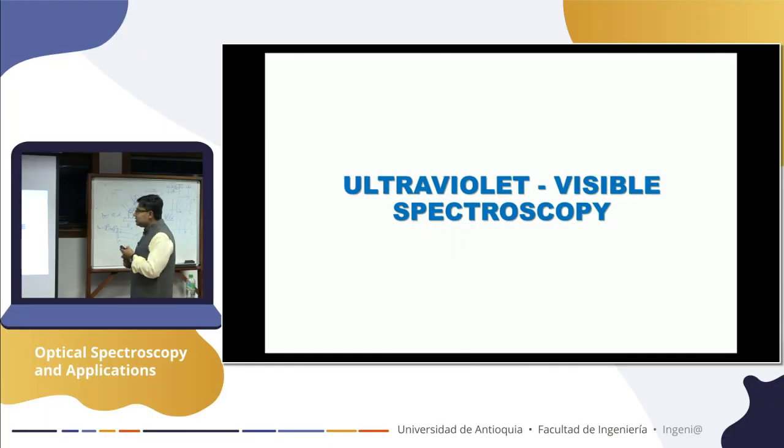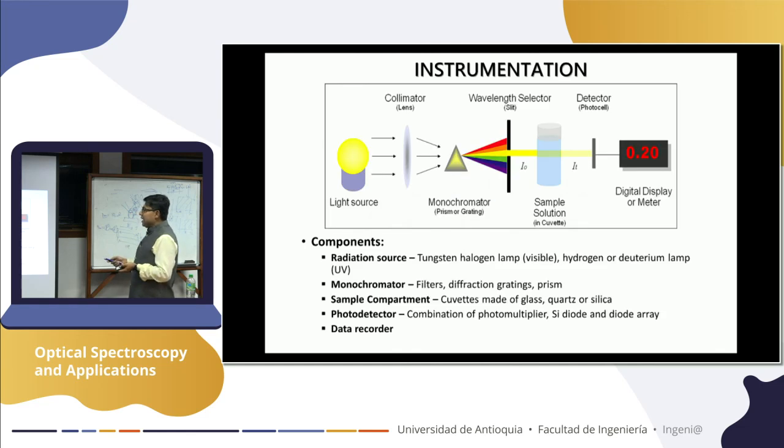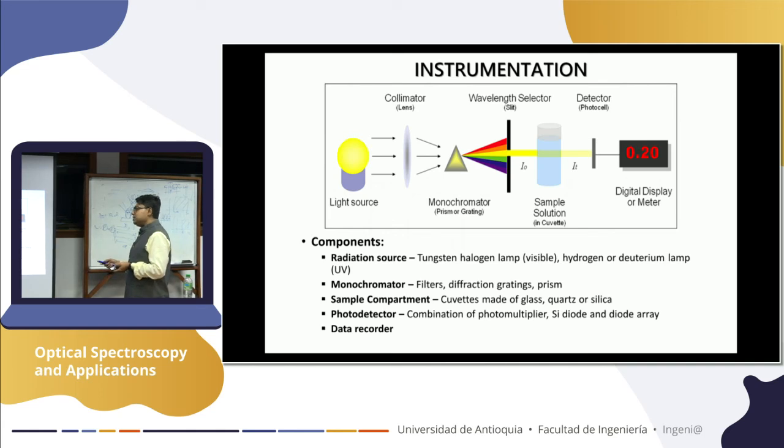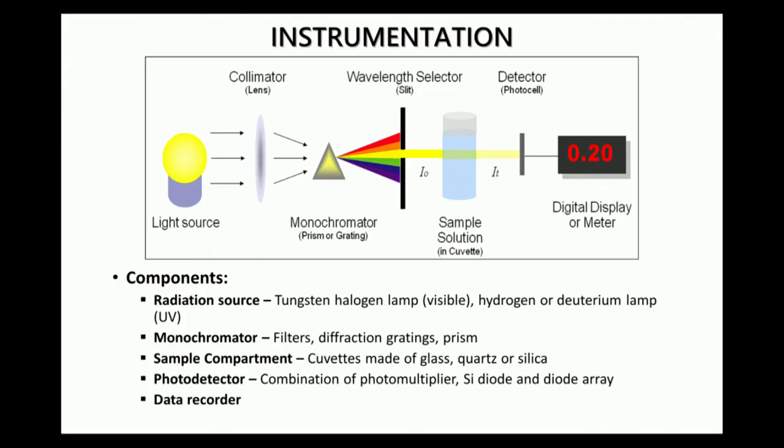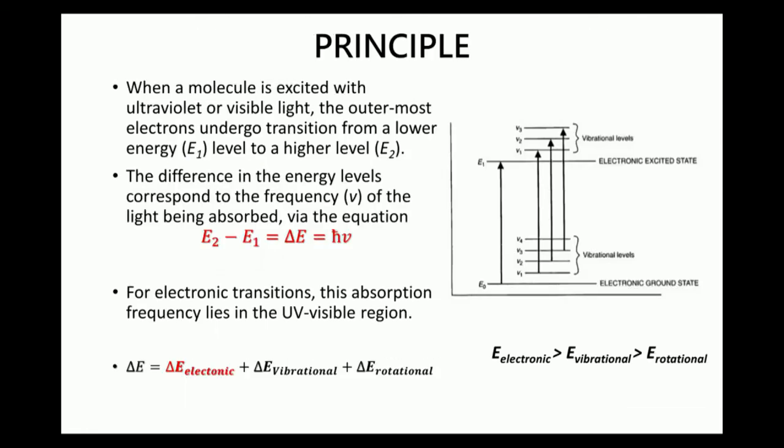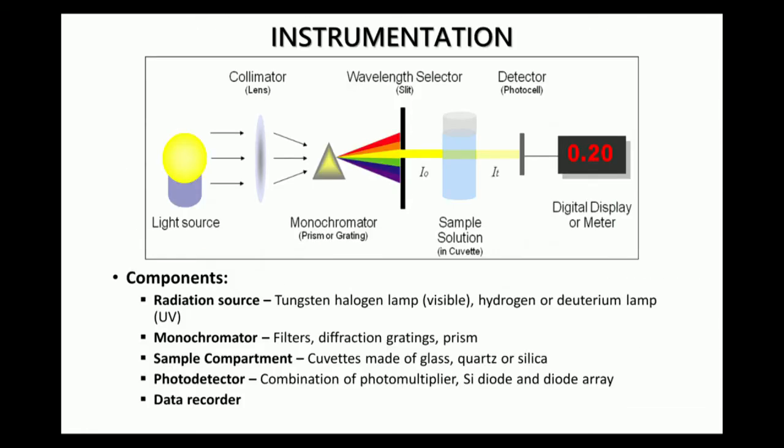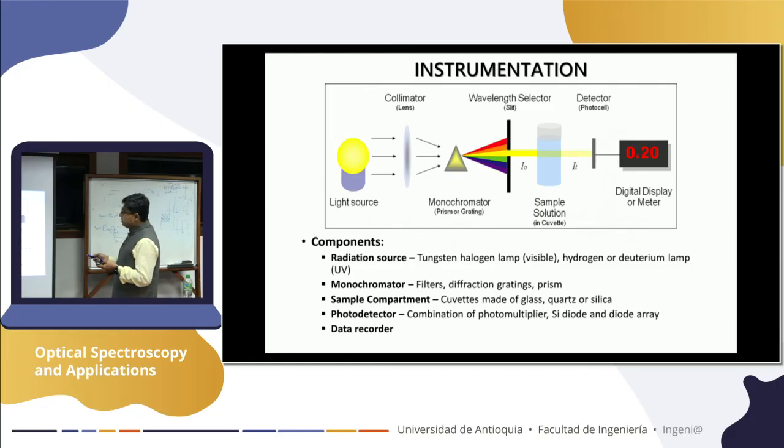We started with UV spectroscopy, where we have a light source, disperse the light using a dispersive medium like a prism or grating, and then using a pinhole we allow one wavelength to go through at a time. Each wavelength illuminates the sample, and you measure the light intensity coming through the sample.